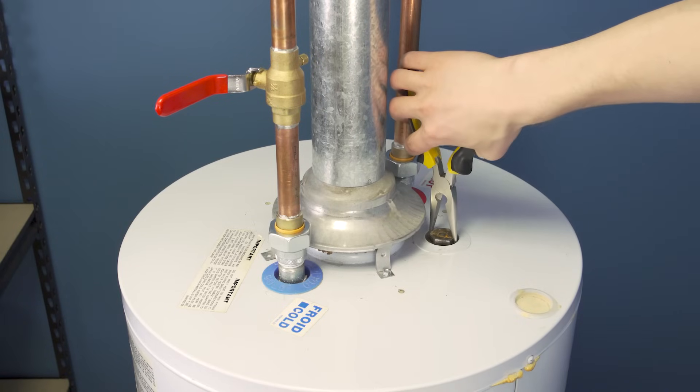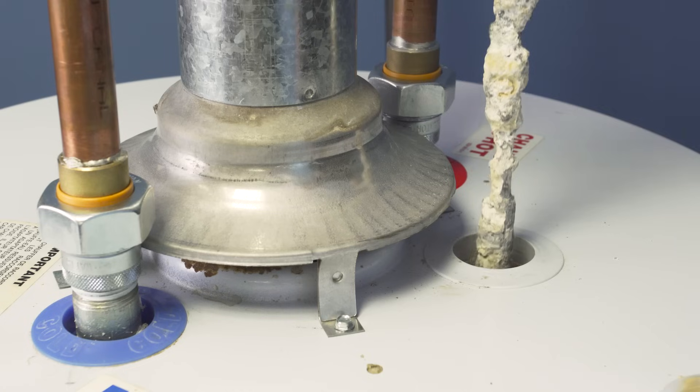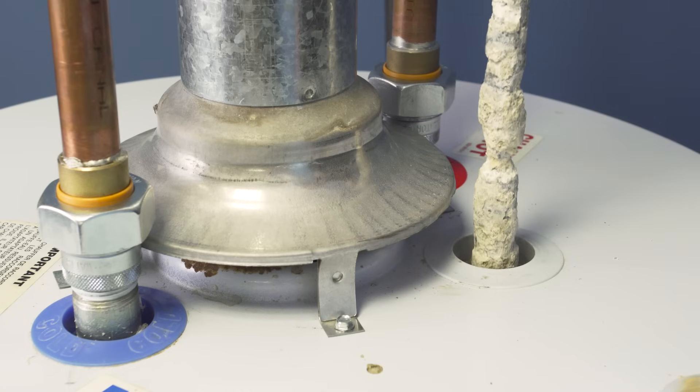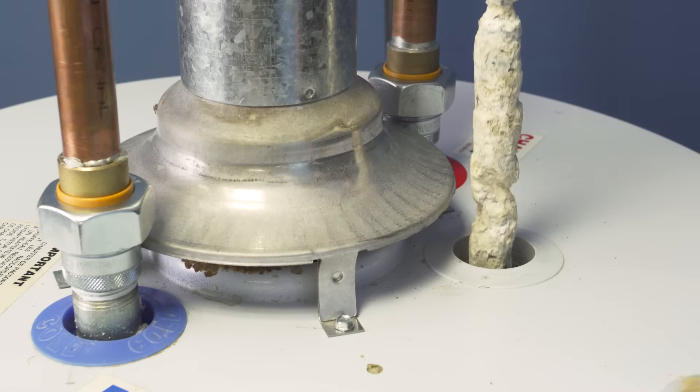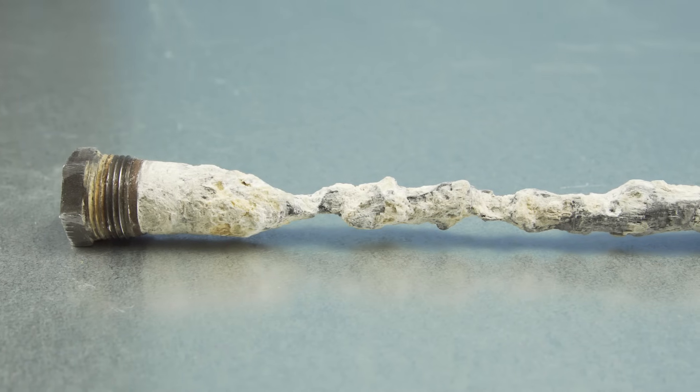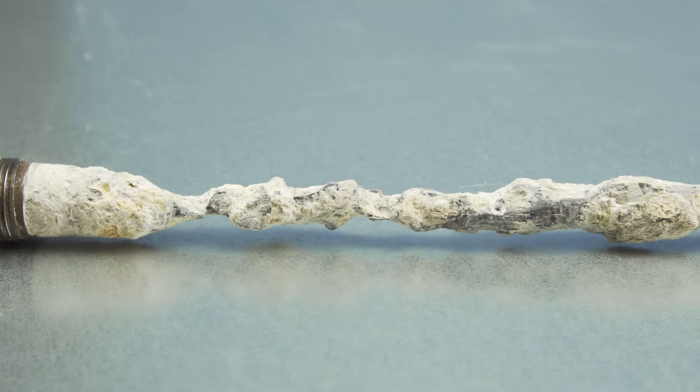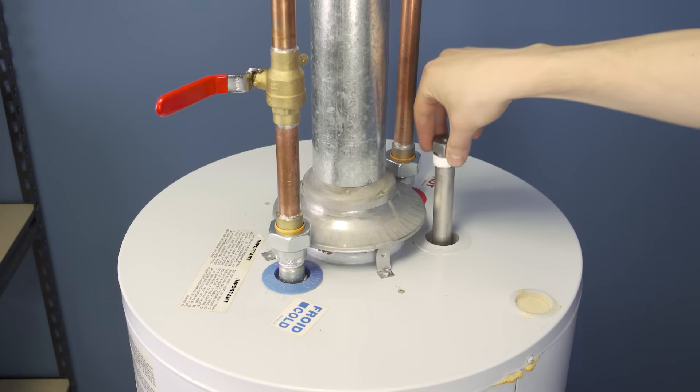Now use the needle nose pliers to remove the anode rod. Each year that you check the anode, take note of what has changed. Most anode rods will last 4 to 6 years, but this depends on the pH and purity of the water. If you can see the bare steel core, or if the rod is completely encased with calcium, then the anode will have to be replaced.